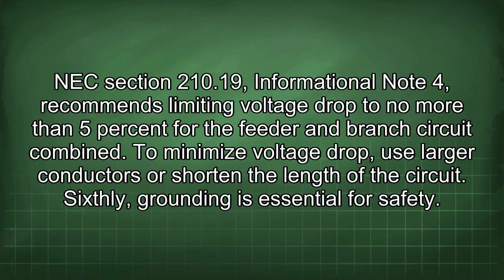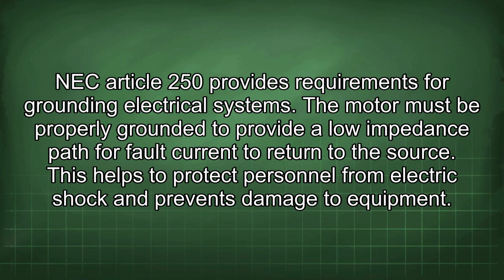Sixthly, grounding is essential for safety. NEC Article 250 provides requirements for grounding electrical systems. The motor must be properly grounded to provide a low impedance path for fault current to return to the source. This helps to protect personnel from electric shock and prevents damage to equipment.